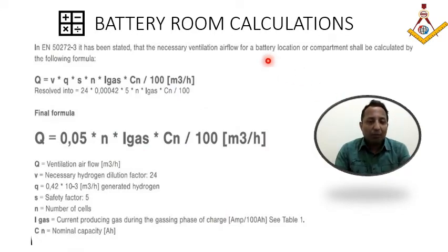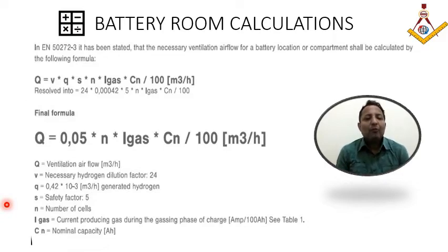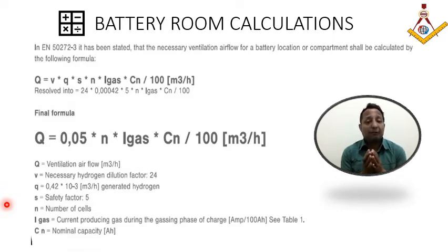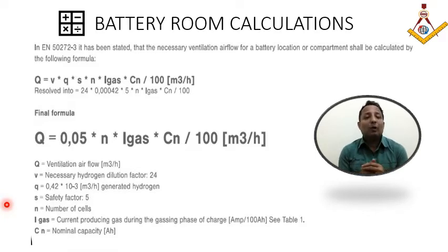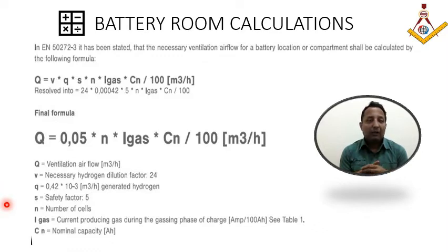The battery room is a very important aspect as far as marine offshore oil and gas is considered. The battery room basically consists of batteries which are normally for the UPS system. The batteries play a very important role to have uninterrupted power, so the batteries always need to be charged. And when battery charging is required, it releases a certain amount of hydrogen, and hydrogen is a hazardous gas.